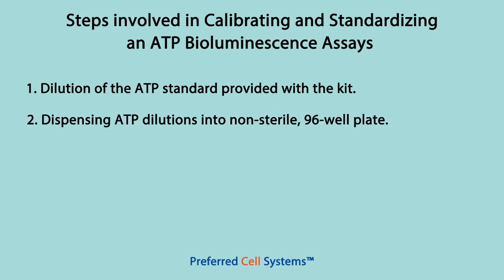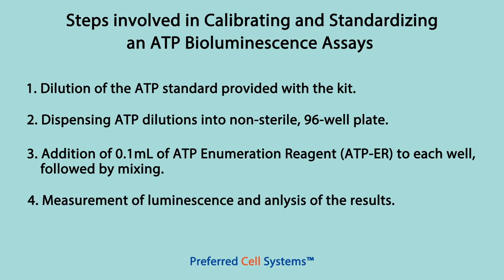There are four individual steps to calibrating and standardizing an ATP bioluminescence assay. First, dilution of the ATP standard provided with the kit. Second, dispensing each of the ATP dilutions into the 96-well plate provided, and also dispensing the low and high controls after the ATP dilutions. Third, addition of 0.1ml of the ATP enumeration reagent to each well, followed by mixing. And finally, measurement of bioluminescence in the luminescence plate reader and analysis of the results. Let's now go to step one of the protocol: dilution of the ATP standard.